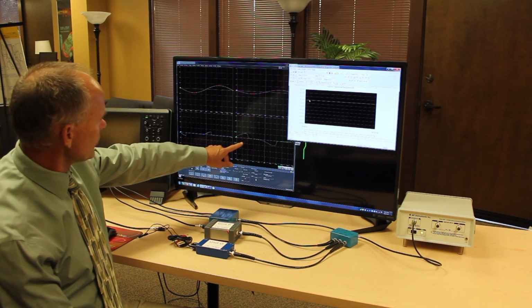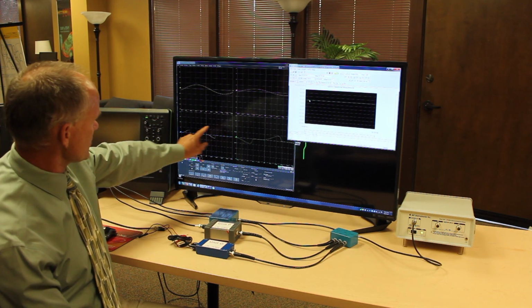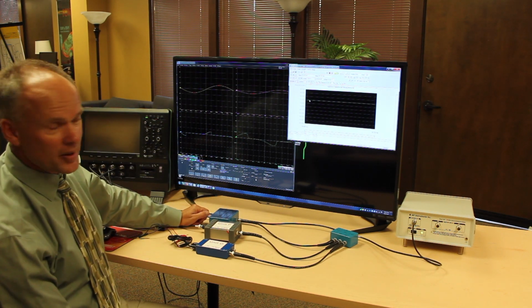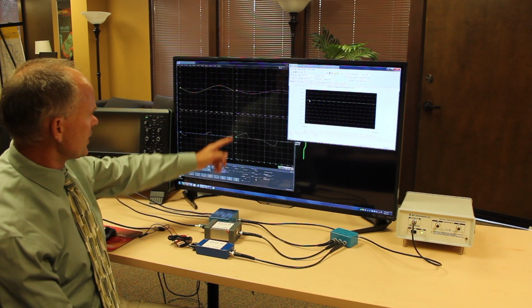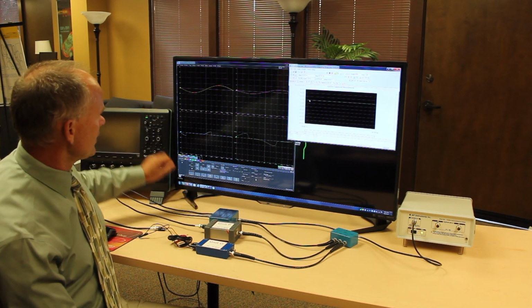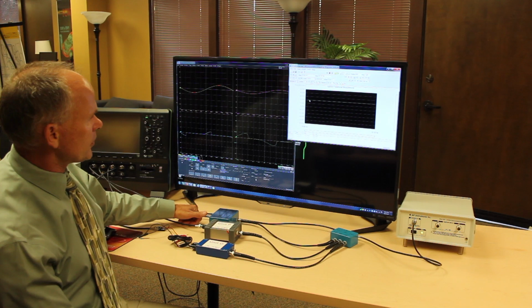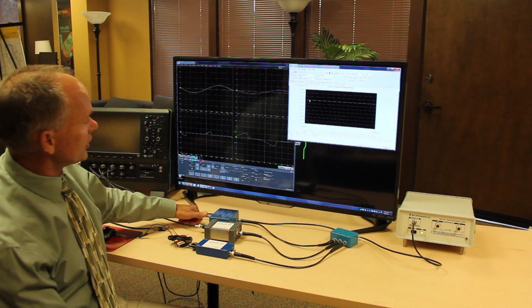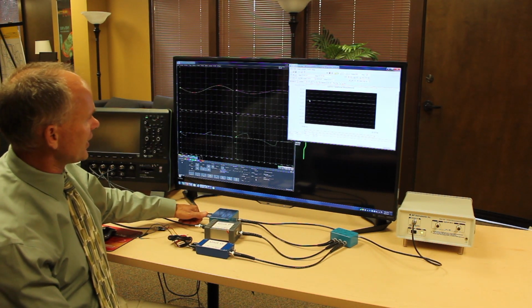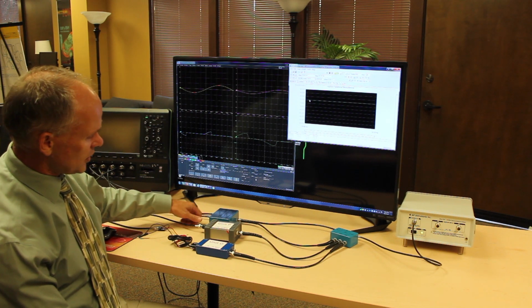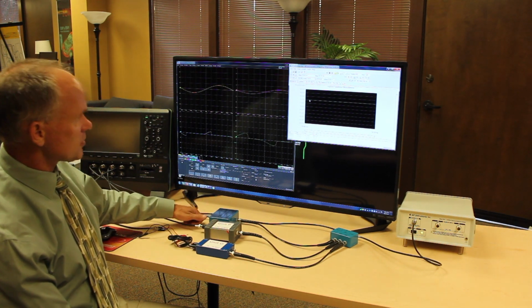Unit O also has distortion. These are different from each other, obviously a different transformer being used here. But again, this one is saturating very badly and is really not usable with a 1 volt signal down at 10 Hertz, which is well within the specification where this is supposed to be working.